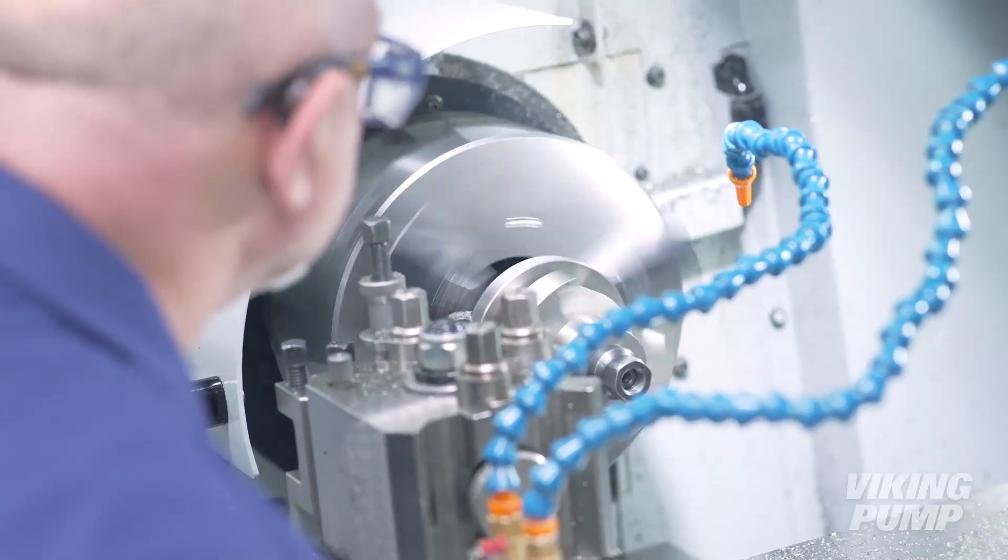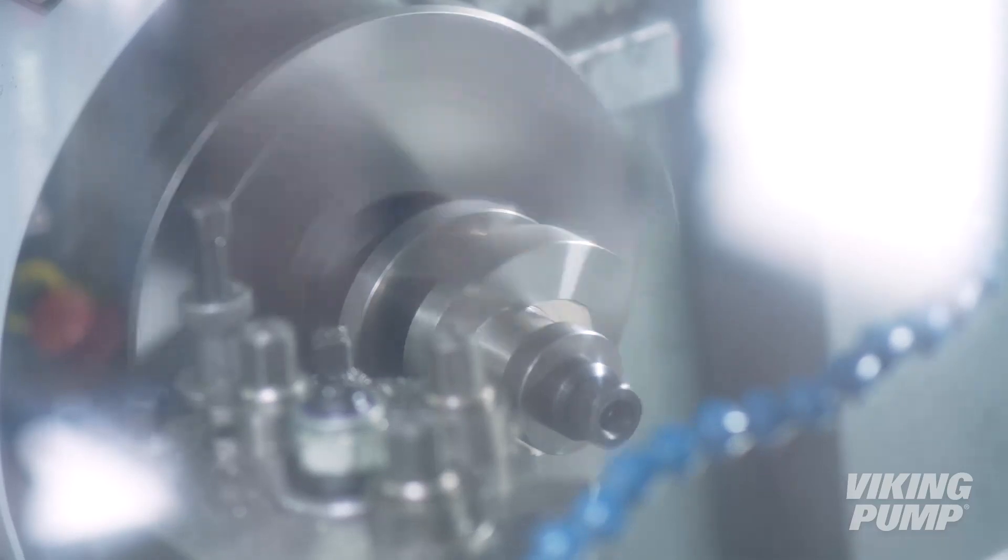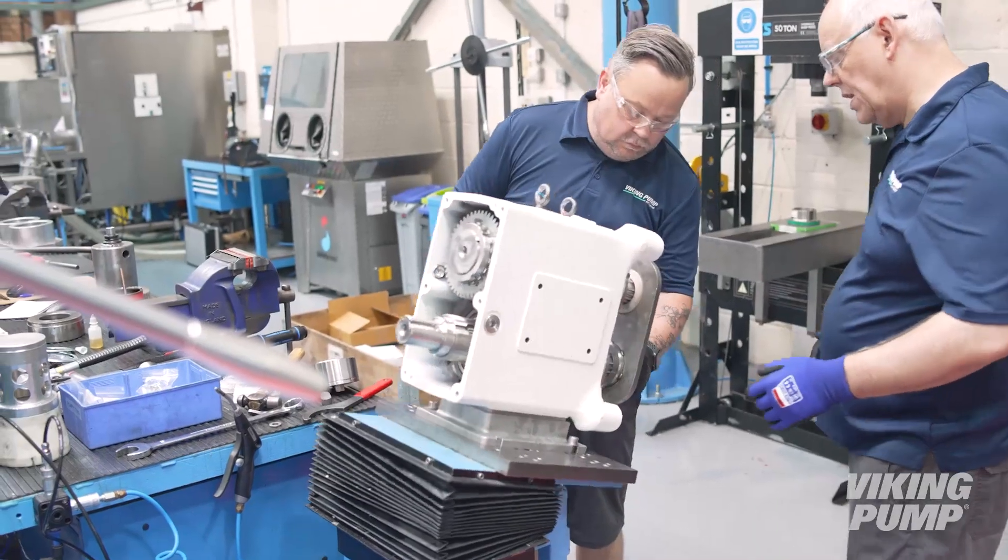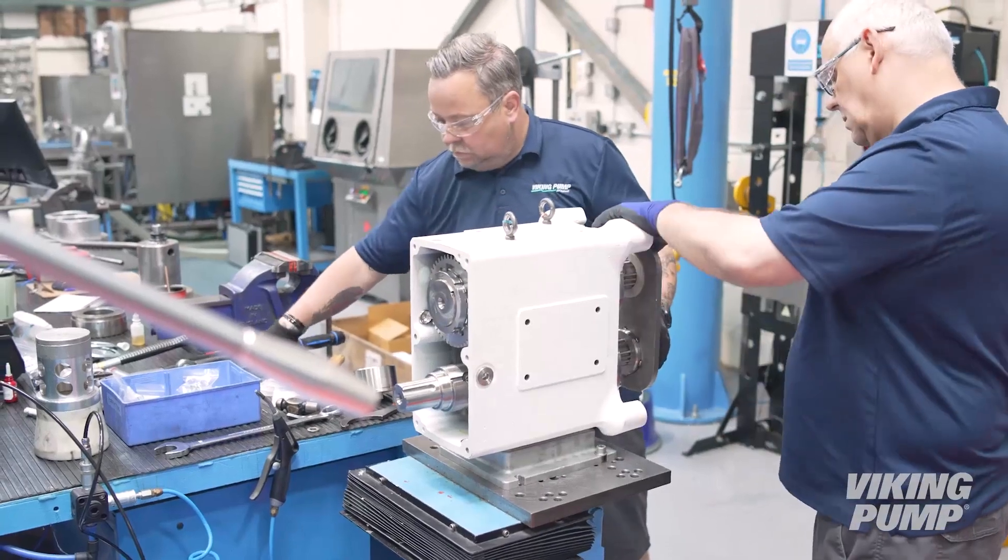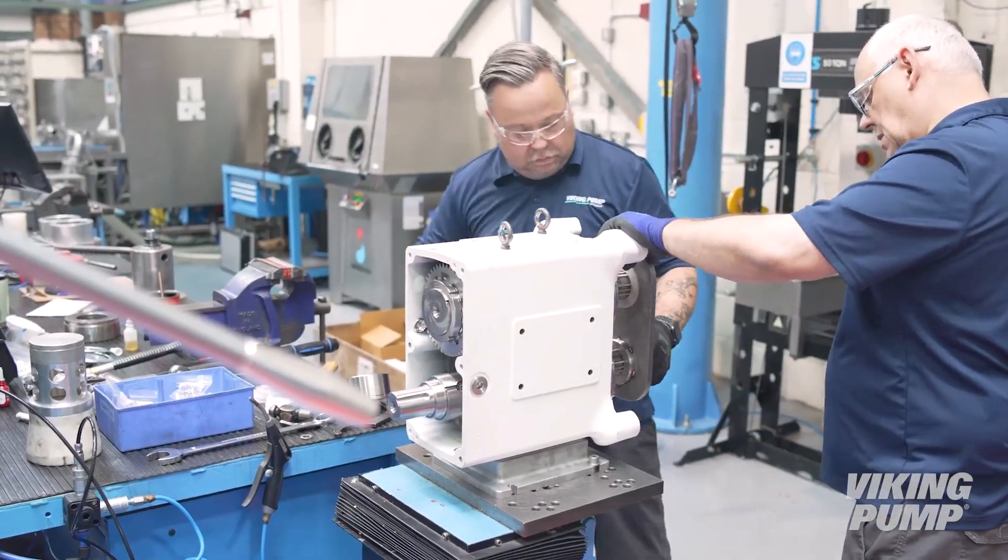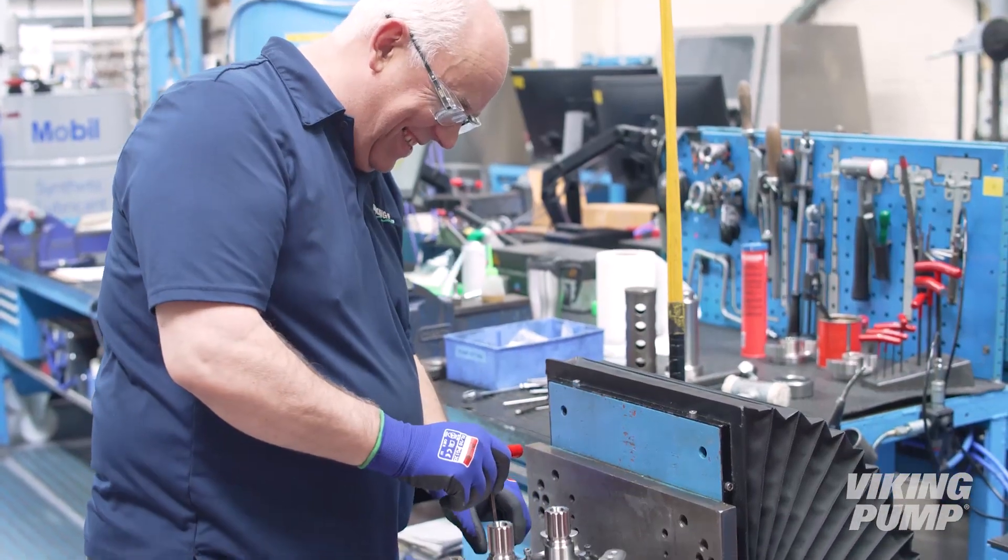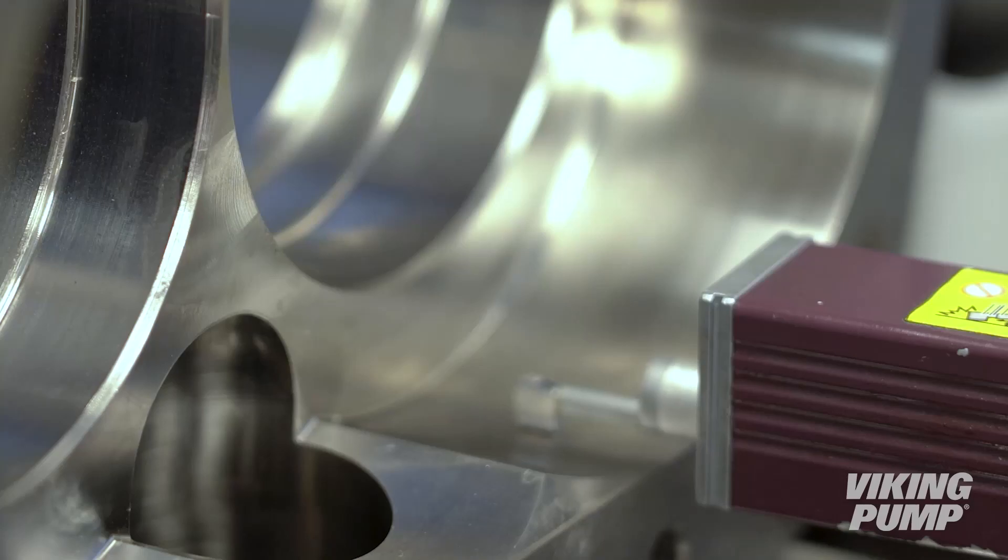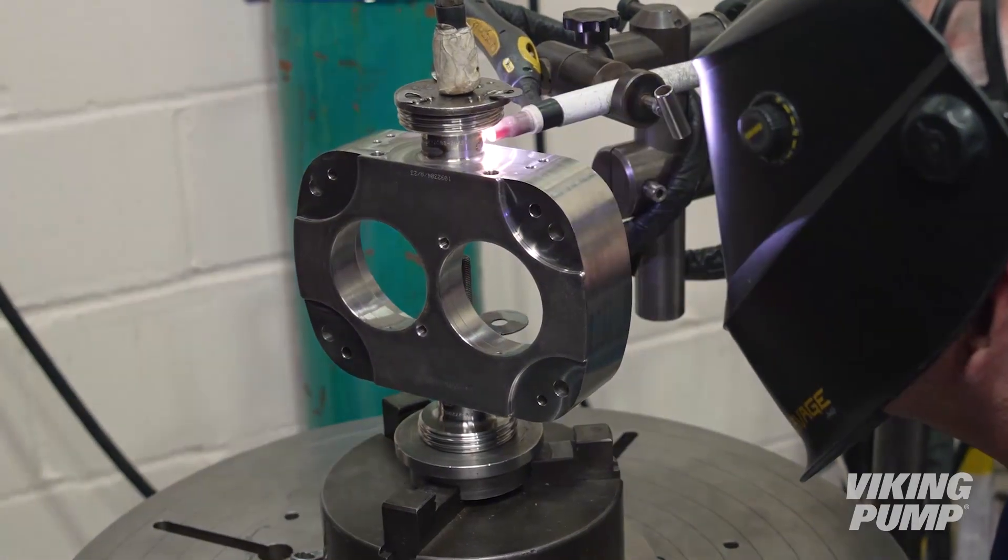If minor part modifications are needed, like for instance the temperature classes on rotors, that is done using in-house equipment. Pumps are then assembled by our skilled team of pump fitters and the assembly process does include various steps along the way like taking surface finish readings, ferrite levels, and seam welding the ports.